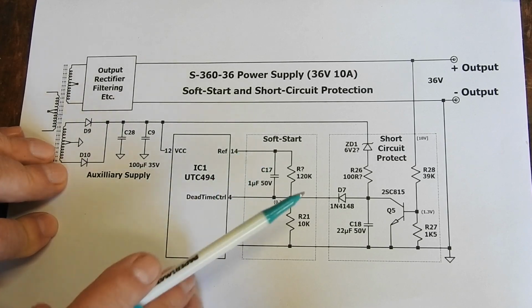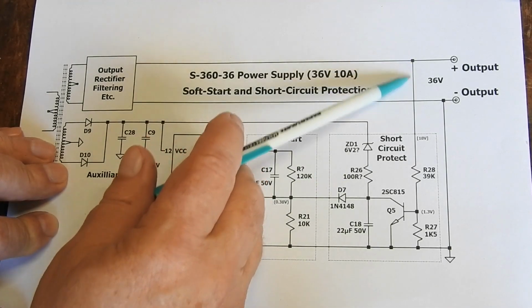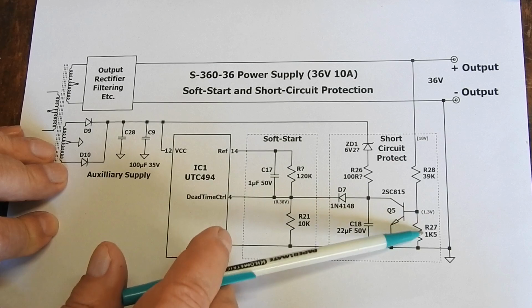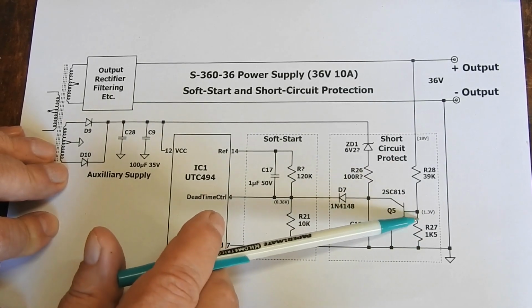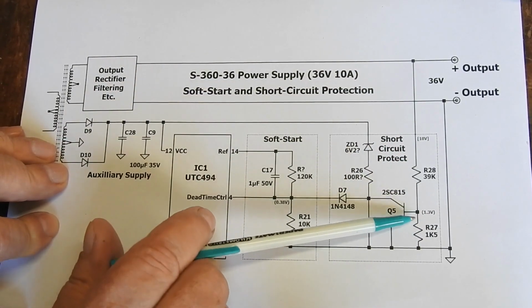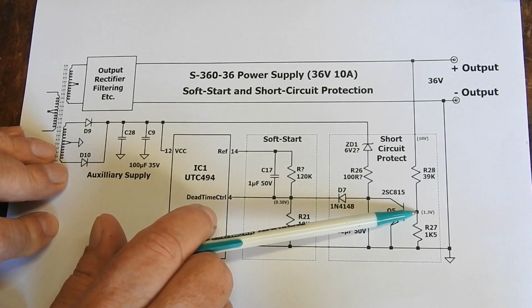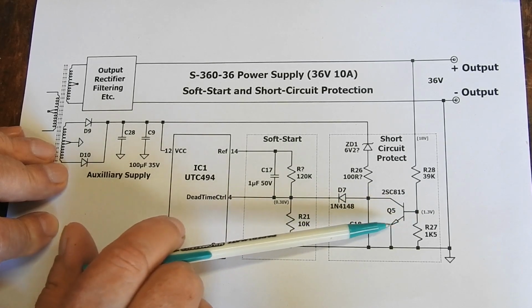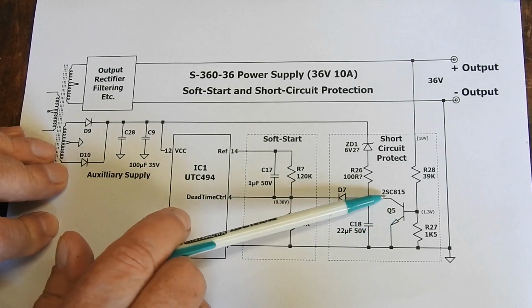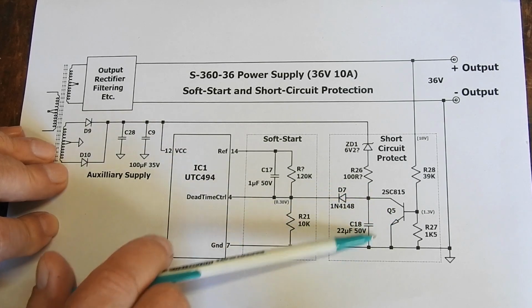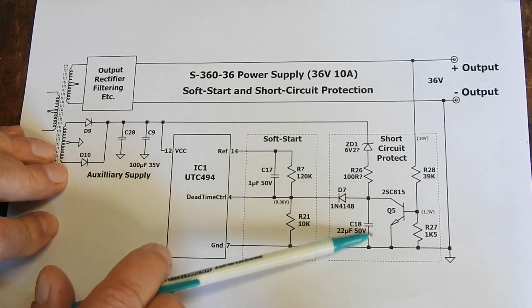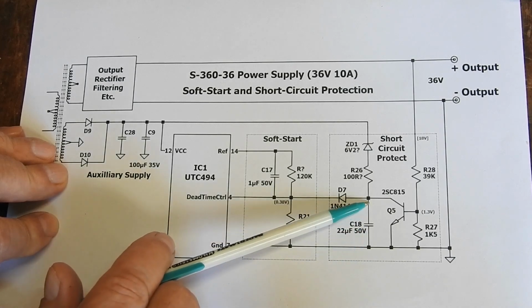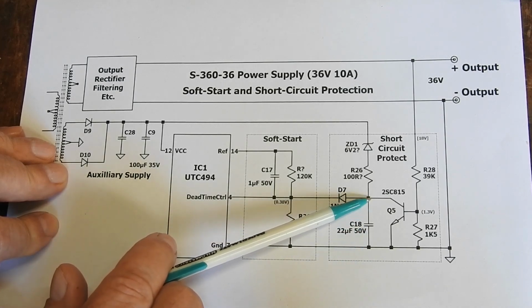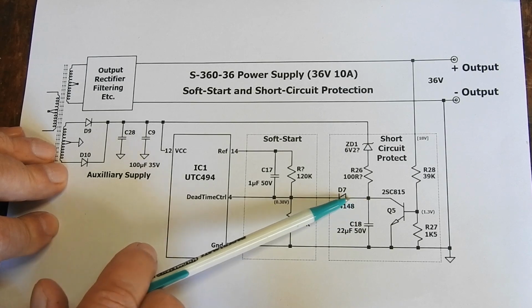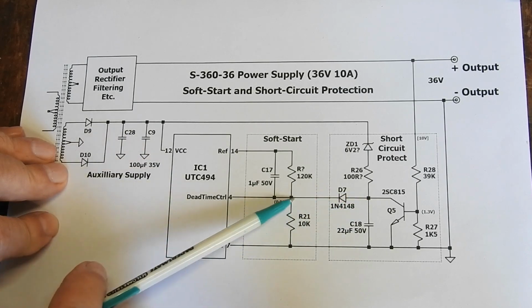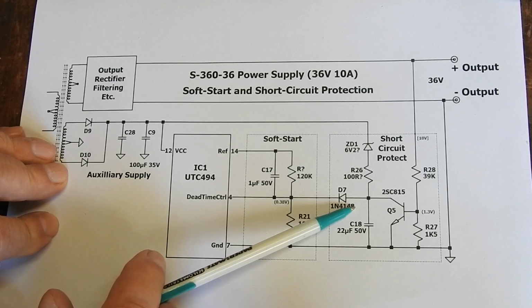The short circuit protection works by monitoring the output of the power supply through this voltage divider. Now at 36 volts that will be producing 1.3 volts, which is enough to turn on this transistor Q5, which short circuits this capacitor. So there's no voltage in that capacitor, and because that's now at 0 volts, that diode prevents it doing anything to the dead time control.